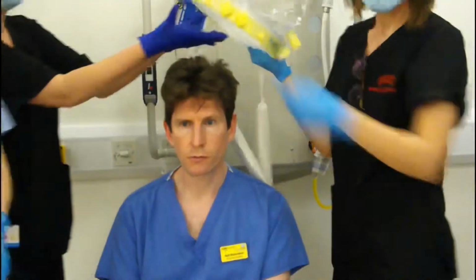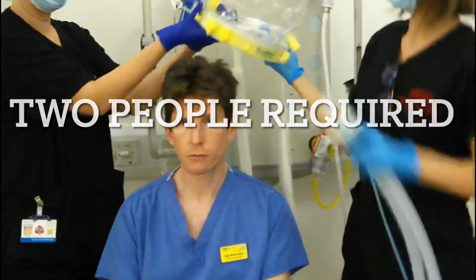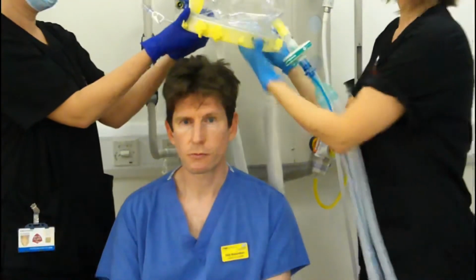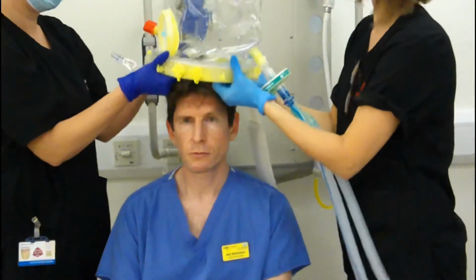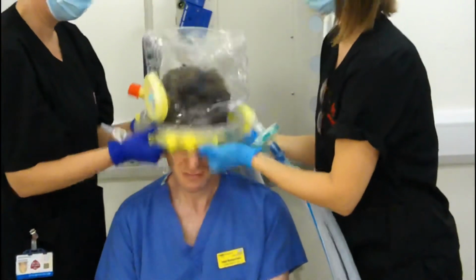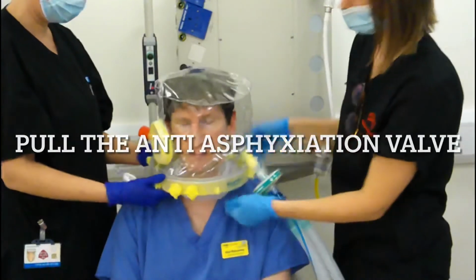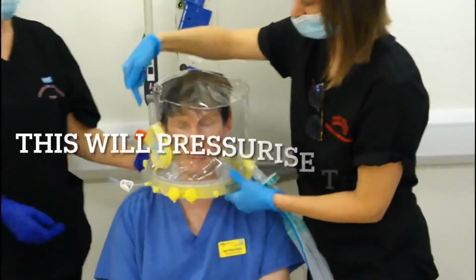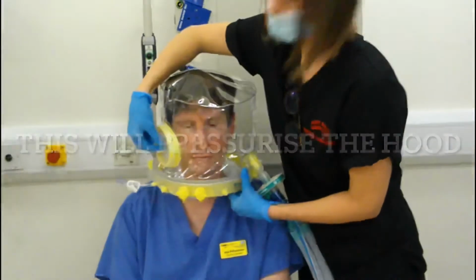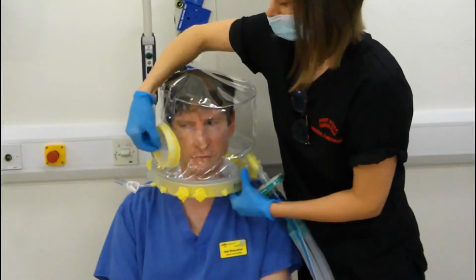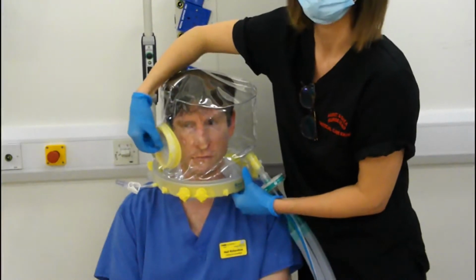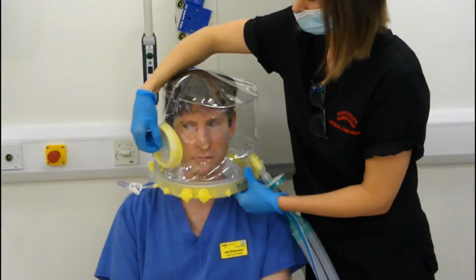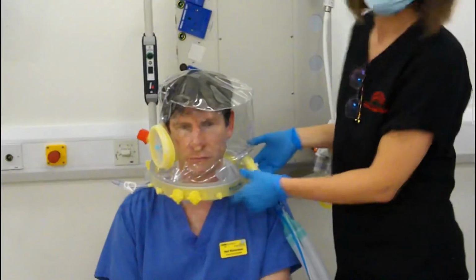So we're just going to get that attached. Right, open up the seal nice and tight, and that just slips over the patient's head, and the ventilation is already running. Now for the hood to inflate, the most important part is pulling the anti-asphyxiation device. Once you open that, the hood will inflate.